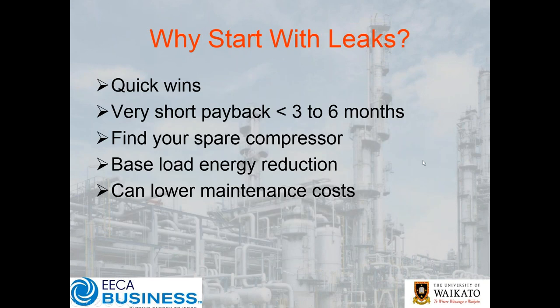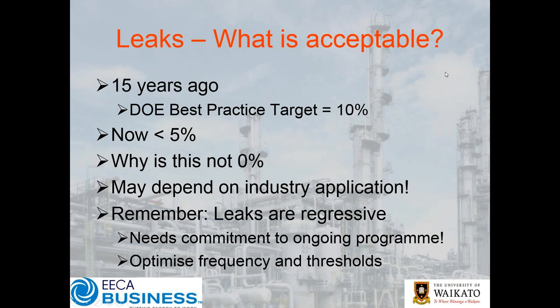We're going to go through this list one by one and look at what we actually need versus what we're currently using. Obviously, the first thing is to start with our leaks. Some will say, why bother? The simple answer is it's a quick win — generally a very short payback. You can free up a spare compressor. It's a baseload reduction and you can achieve maintenance savings. Fifteen years ago the US Department of Energy best practice target was about 10% of total demand as an acceptable leak rate; nowadays that's dropped to 5%.